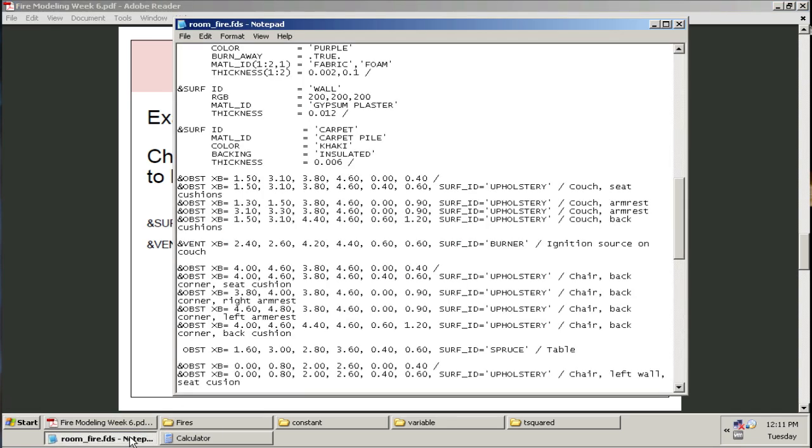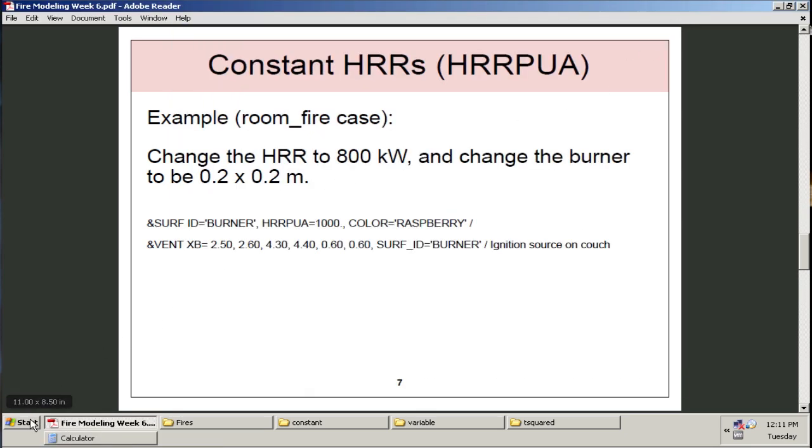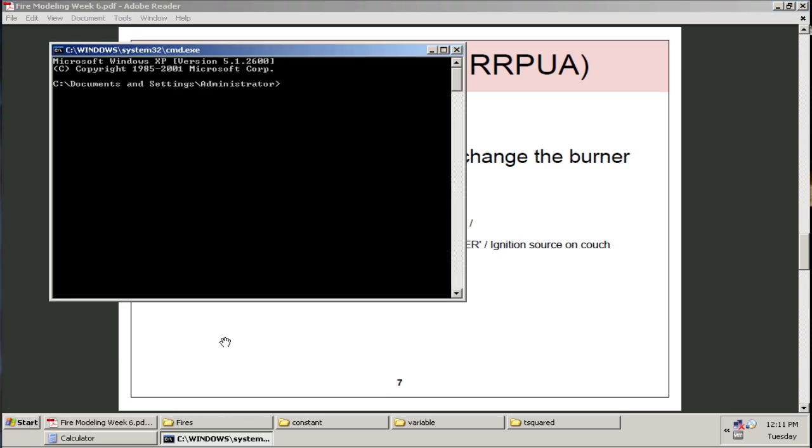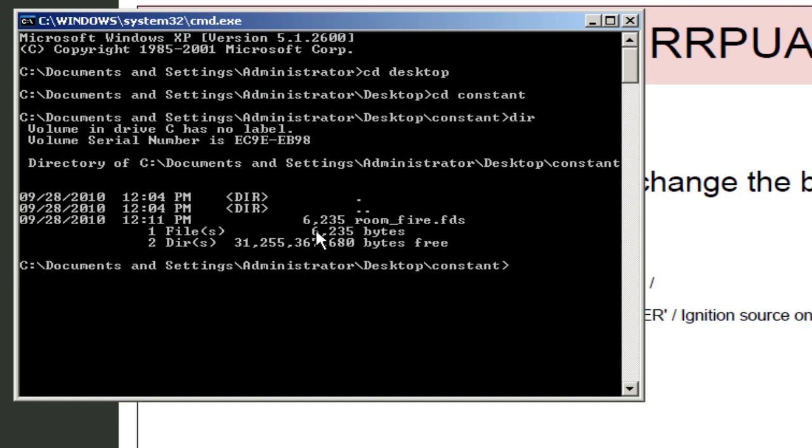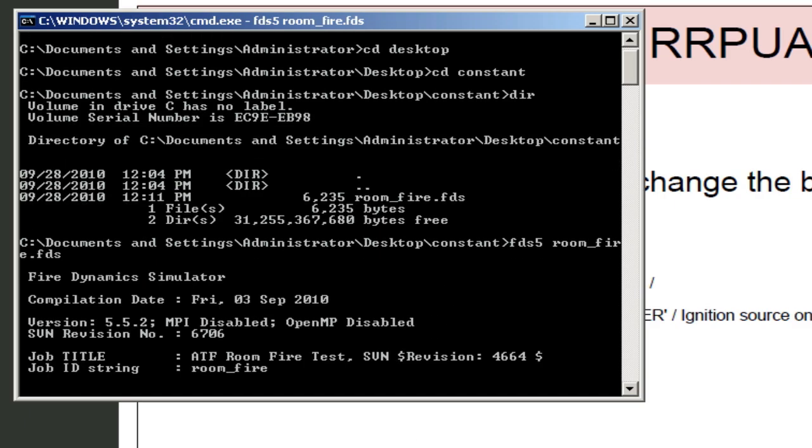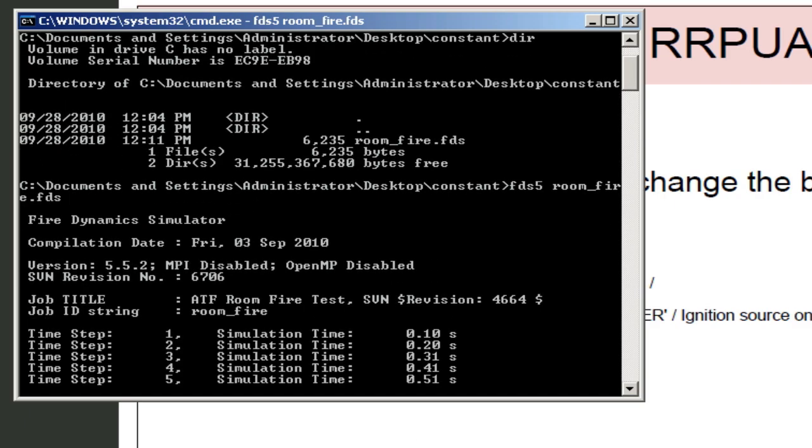What I'm going to do is I'm going to go ahead and run this FDS case. So, I'm going to save my edits and proceed to run. I can go to start menu, run, type cmd to get to the command prompt. And I can type cd desktop, and I can type cd constant to get into that directory. If I type dir, there's room_fire.fds. So, at this point, I can type fds5 room_fire.fds. And hit enter, and that case will run. I'll go ahead and let that case run because we'll use it at the end to verify that we have the correct heat release rate in FDS. So, that case is running.